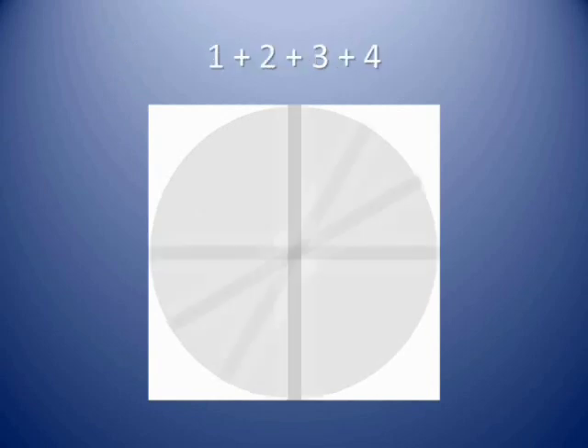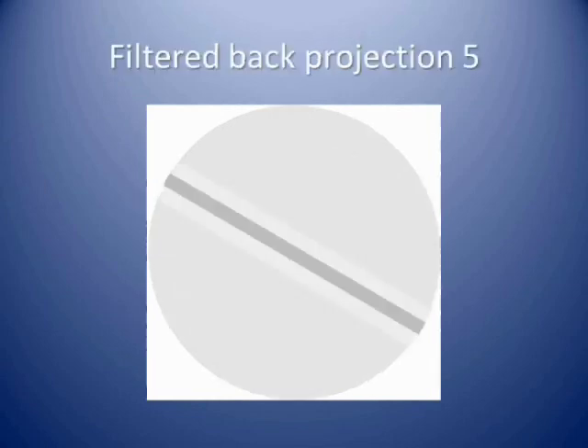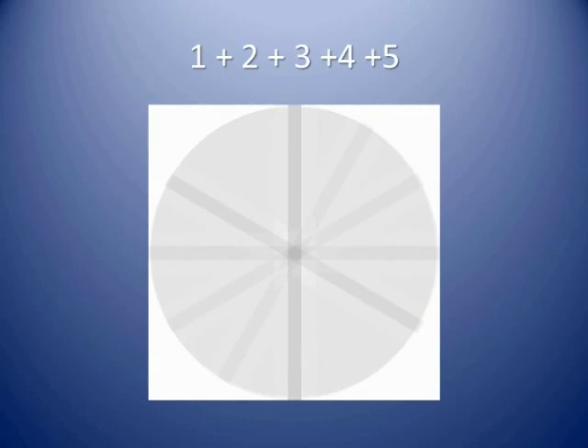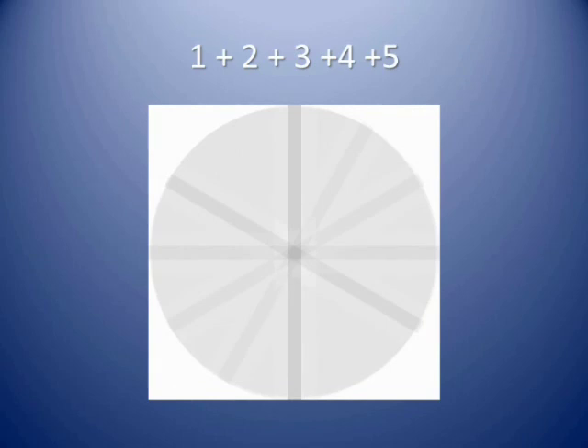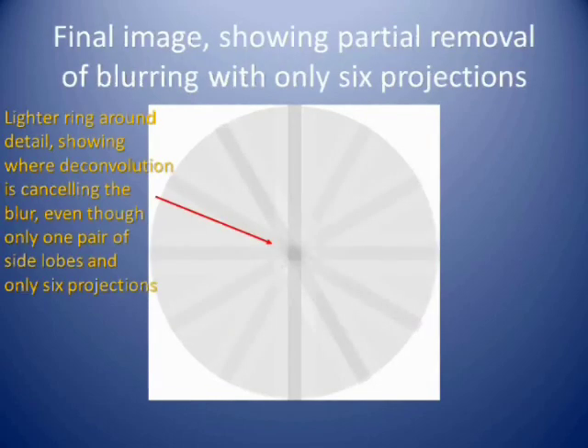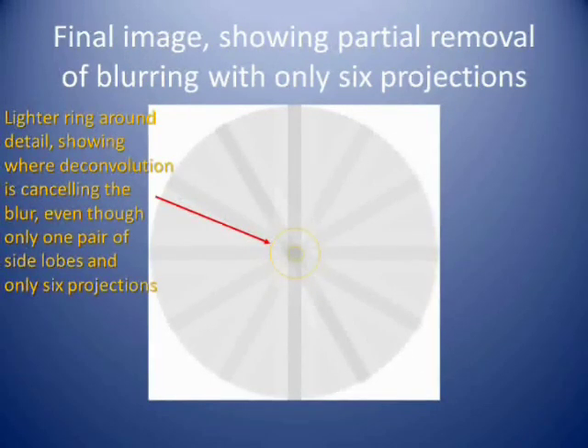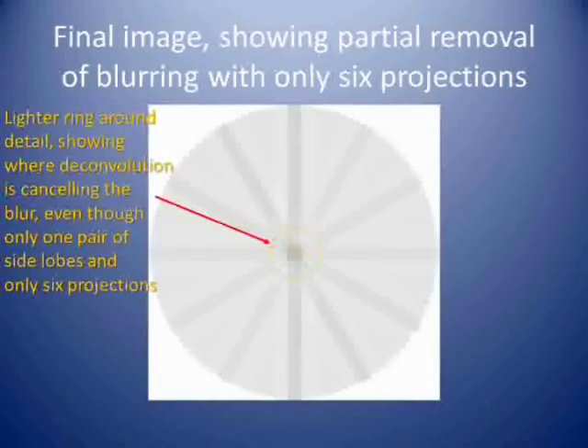The lighter regions correct for back projection blurring, resulting in cancellation of the back projection blur, provided that enough projections are used and provided the convolution kernel is appropriately designed. This little example is intended to show the principles, and of course does not result in a perfect back projected image.